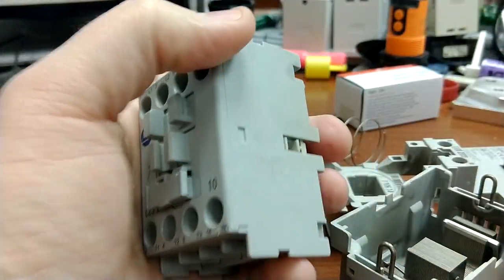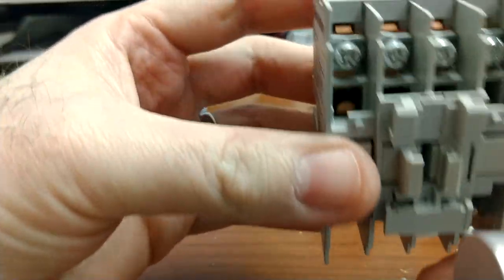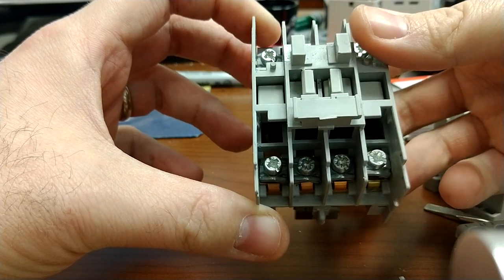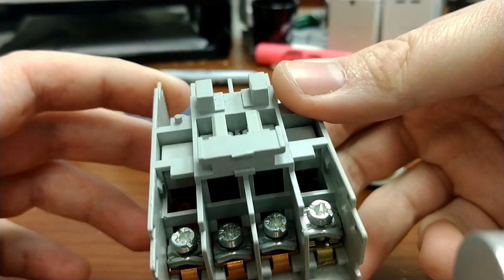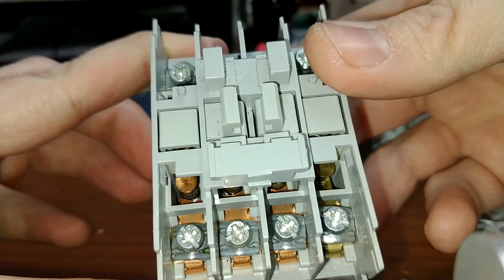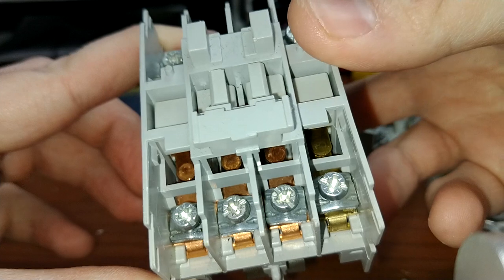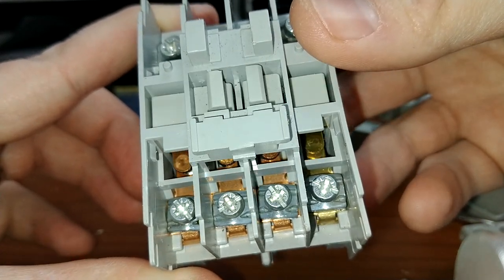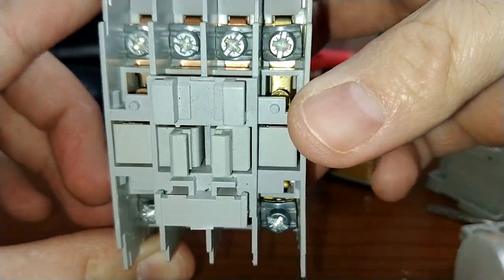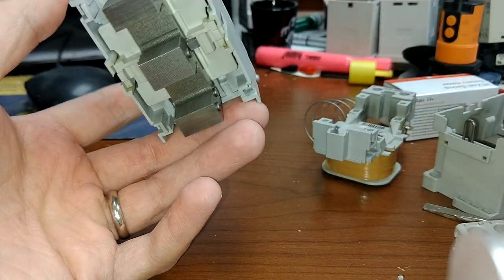So, let's see if I can break this apart, because why not? Let's get in there. Break. Let's get in there and show you what's on the inside. Aha! So now we can take a little bit better look in there. My lighting is garbage. But you can see, clearly, let's see, can you, you can kind of see in there, if I, maybe, I'm trying to get the better lighting. See it now. Hey, lighting. You can see the contacts in there as it comes down. So right now this is not engaged, but once that magnetic field goes down, you can see how it connects. And there's your ancillary contacts are electrically isolated. That's doing the same thing. Really cool, huh? But this is how a contactor works.